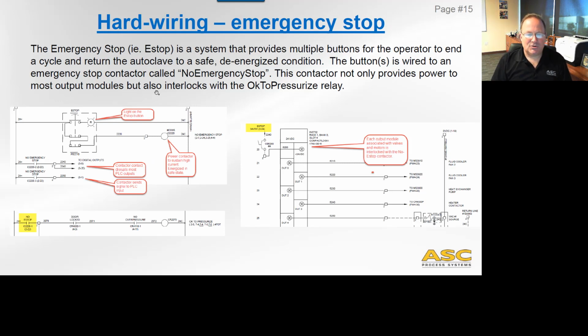Emergency stop. So here's the emergency stop circuit, and depending on the size of autoclave, there might be one emergency stop button or multiple. There can be up to 10 of them in very large autoclaves. And they're all going to be wired in series and providing a single sort of huge stop of all outputs on the autoclave. And the way that that's done is basically that e-stop is tied into a contactor or a series of contactors, and that contactor, each contact is then routed over to, for example, here, all the digital output modules. So what it's doing is when we don't have an e-stop, meaning everything's good, we're providing power to all of our output points. But when we interrupt that power by hitting e-stop, all those outputs shut off.